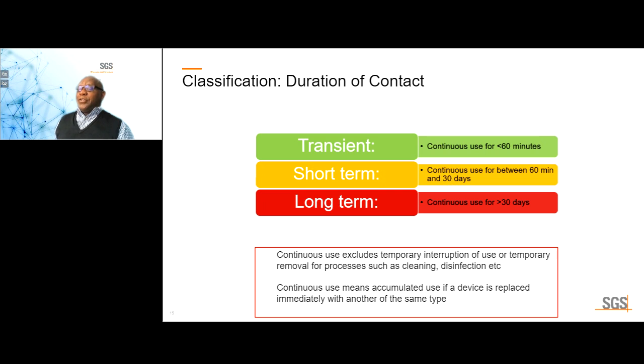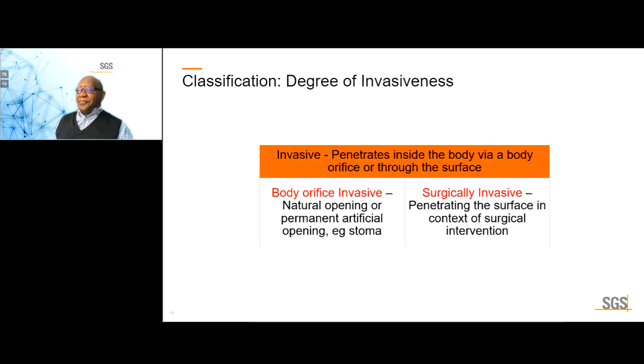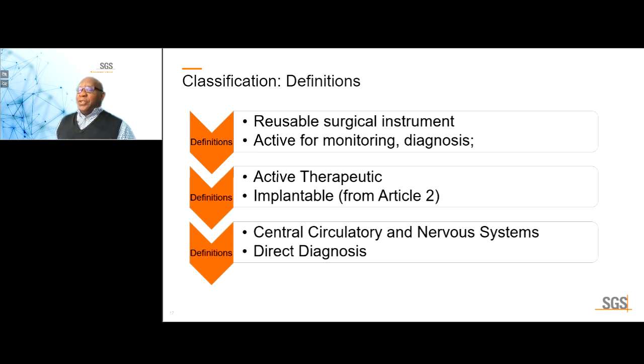So you got to keep in mind that continuous use means accumulated use if a device is replaced immediately with another of the same type. Invasiveness, or degree of invasiveness. Invasiveness means the device penetrates inside the body via a body orifice or through the surface. Body orifice invasive is regarded as natural opening or permanent artificial opening, such as a stoma. And surgical invasiveness means penetrating the surface in the context of surgical intervention. And there are other definitions you need to be aware of: reusable surgical instrument, active for monitoring or diagnosis, active therapeutic, implantables, and central circulatory and nervous systems, and direct diagnosis.